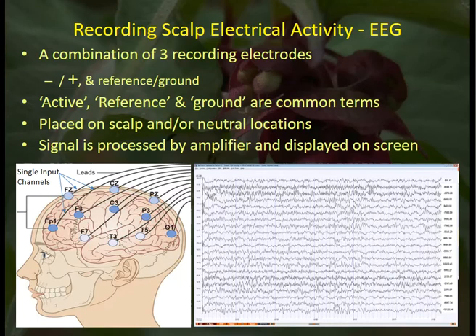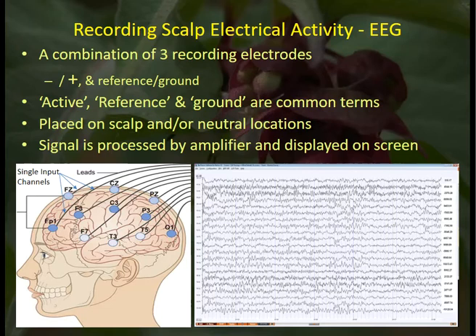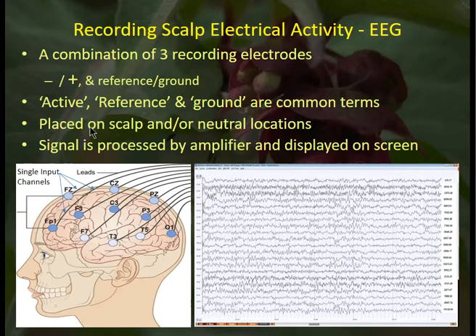Recording a scalp electrical recording from multiple sensors or a single combination of sensors — always remember that it requires at least three sensors to produce an EEG recording: the positive sensor, the negative sensor, and the reference or ground. These active reference and ground sensors are placed on the scalp and/or neutral locations like the earlobe or the mastoid bone behind the ear.